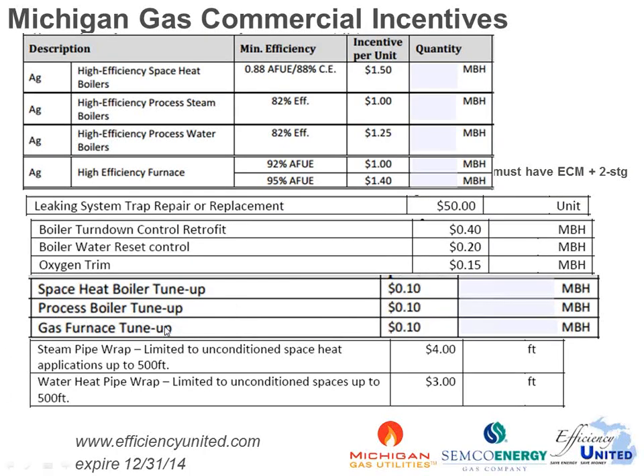Rebates for boilers, for space heating boilers, $1.50 per MBH, got to be 88% and better, which is basically a condensing boiler. There's also rebates for process boilers. Furnaces, either $1 or $1.40 per MBH, depending on 92 or 95% AFUE. It's also got to be two-stage, and it's also got to have an ECM to qualify. There are some boiler rebates for combustion control management stuff, oxygen trim, turn down, water reset, 20 cents, etc.